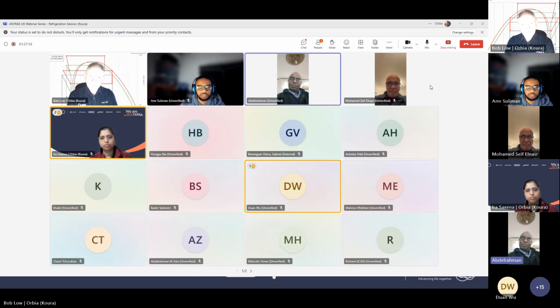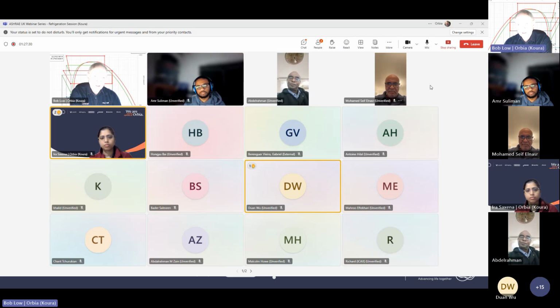Is there any update on the F-gas regulation? The latest update was in 2014. Is there any update concerning this new refrigerant? That blend, 473A, has a GWP of 1800, and the current threshold is about 2500, I think, for minus 50 C and colder. So it's comfortably under. And in America there are some exemptions, but even where it isn't directly constrained, some system makers want to move away from R23 because of the extremely high GWP. So we're working with people in all three of the main continents right now on that.